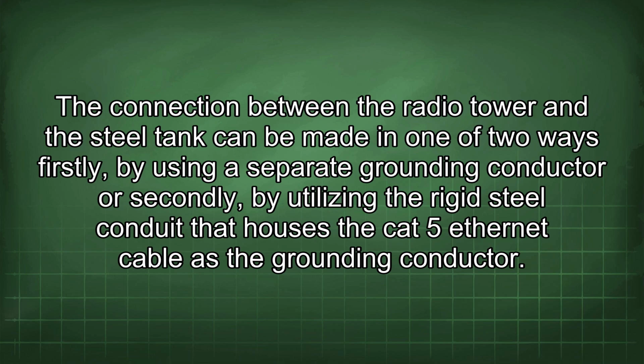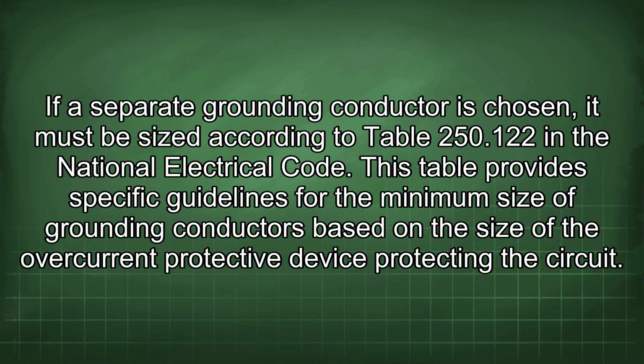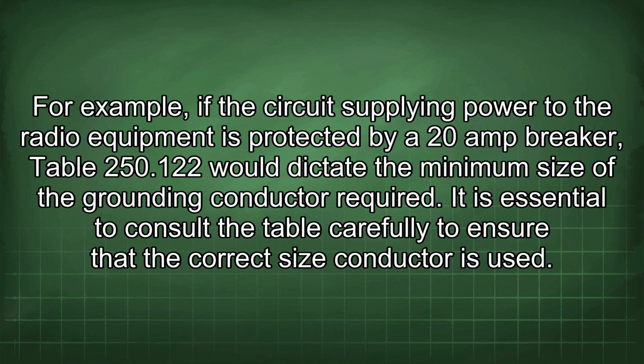The connection between the radio tower and the steel tank can be made in one of two ways: firstly, by using a separate grounding conductor, or secondly, by utilizing the rigid steel conduit that houses the Cat5 Ethernet cable as the grounding conductor. If a separate grounding conductor is chosen, it must be sized according to Table 250.122 in the National Electrical Code. This table provides specific guidelines for the minimum size of grounding conductors based on the size of the overcurrent protective device protecting the circuit. For example, if the circuit supplying power to the radio equipment is protected by a 20 amp breaker, Table 250.122 would dictate the minimum size of the grounding conductor required. It is essential to consult the table carefully to ensure that the correct size conductor is used.